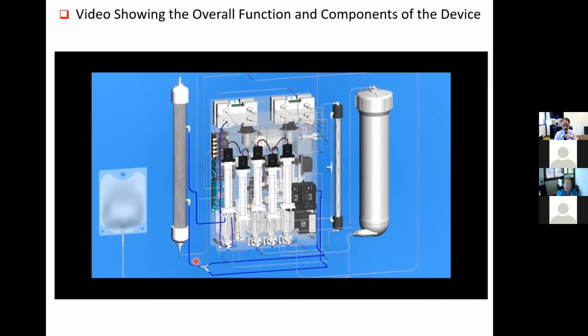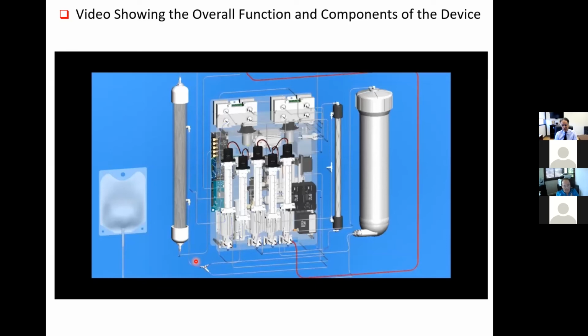The electrodeionization module uses an electrical potential to selectively transport various ions, mainly potassium. The ion-depleted stream is then sent to a level sensor to monitor the flow rate and pumped into the bottom port of the nanofiltration module, which is shown as the second cylinder on the right. The nanofiltration module is used to separate glucose, which needs to be returned to the body, from urea, which needs to be excreted in the urine. The stream with the concentrated glucose is returned to the body through the catheter. The stream with the concentrated urea is shown as the blue flow exiting from the top.